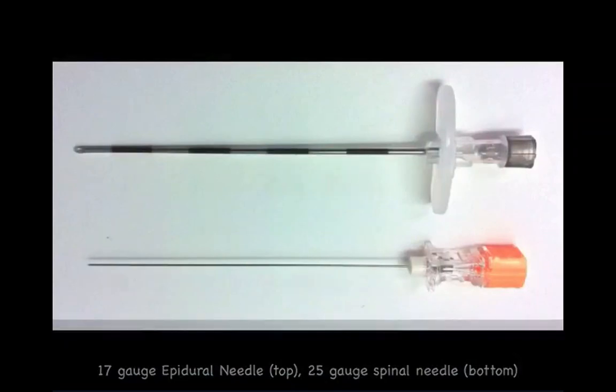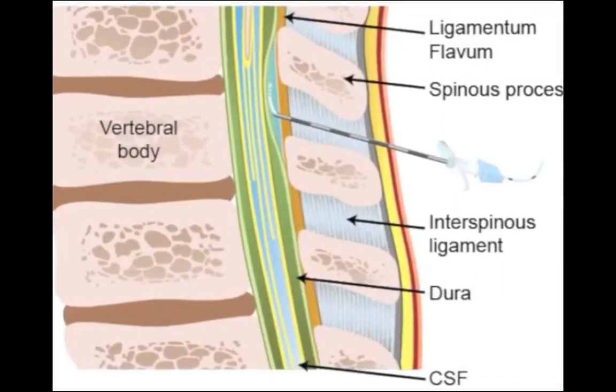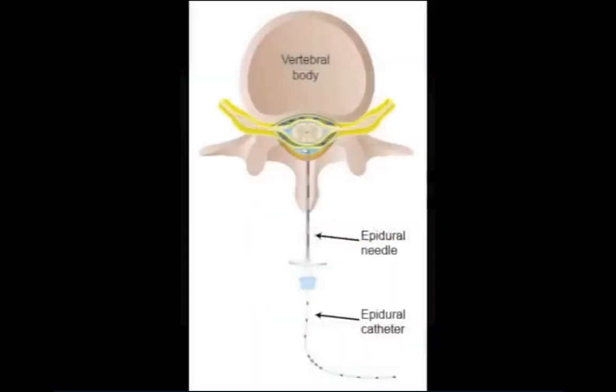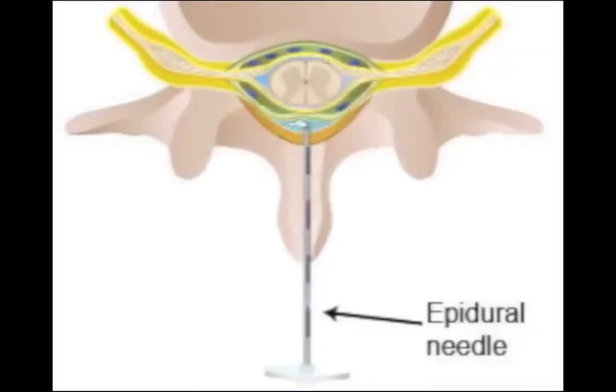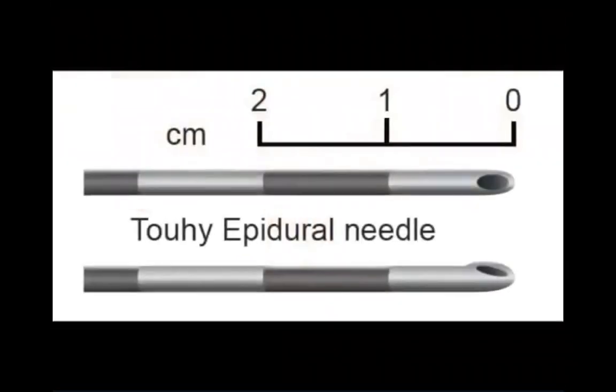An epidural needle has a much wider diameter bore than a spinal needle. The wider bore allows a catheter to be passed through the needle into the epidural space. The tip of the needle is blunt to decrease the chance of it inadvertently piercing the dura, and the tip is also beveled to facilitate passage of the catheter into the epidural space. Centimeter markings along the epidural needle allow the clinician to easily identify the depth of the needle from the skin to the epidural space.